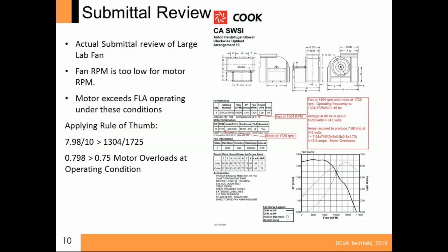I did an analysis real quick. On the right-hand side, you can see my analysis. It says there's 1304 RPM, and the motor is actually 1725. And our brake horsepower, with a 10 horsepower motor, he started off with 7.96. I should say, with his brake horsepower, my eyes are bad, 7.98 or something. And he put a 10 horsepower in it.